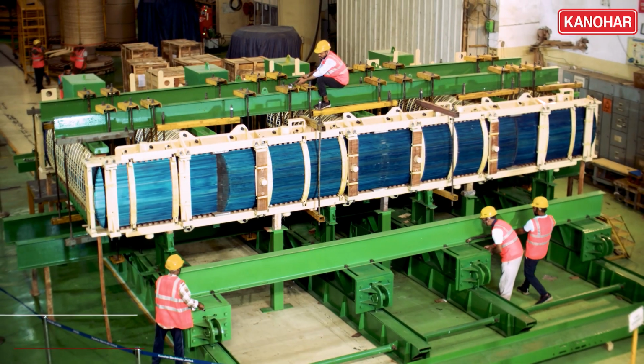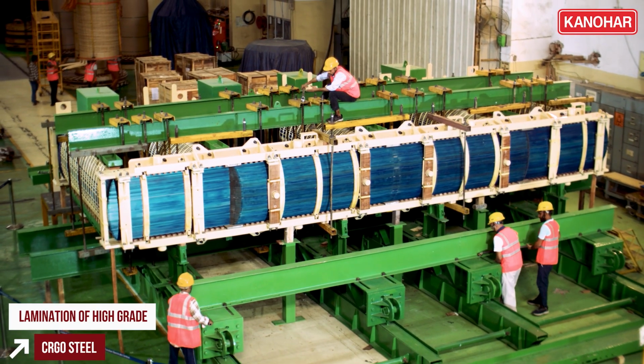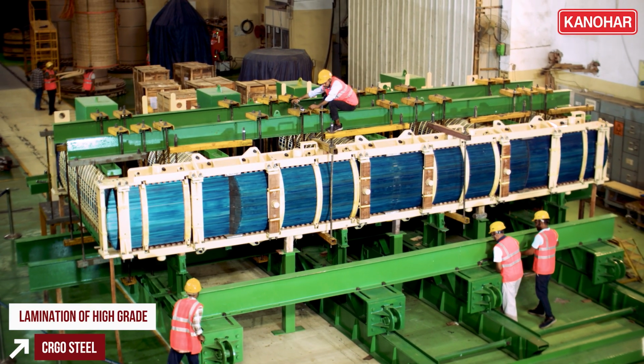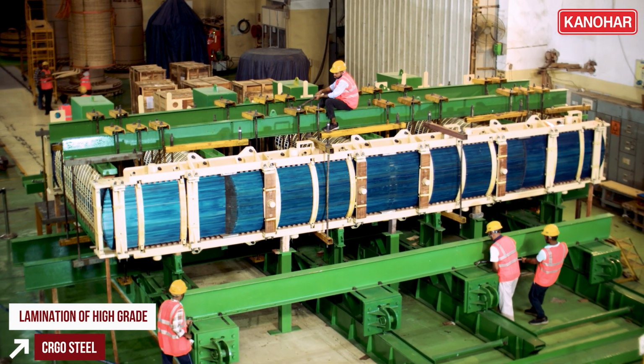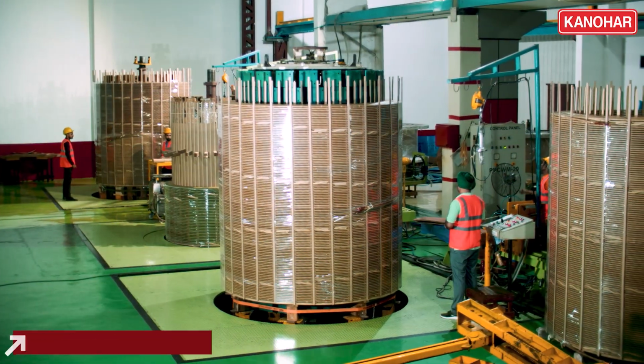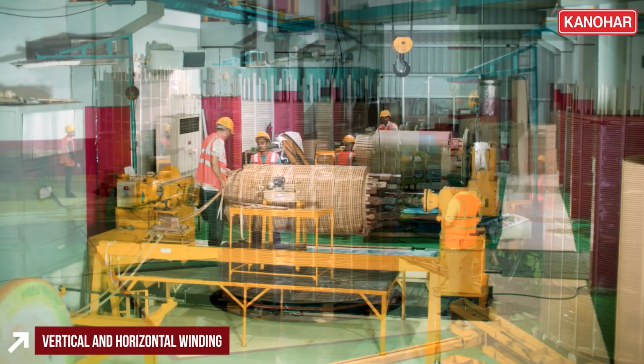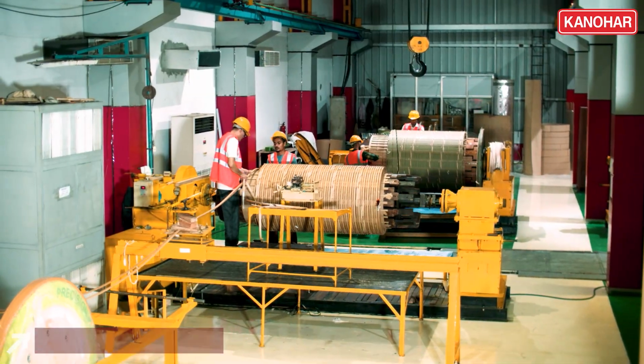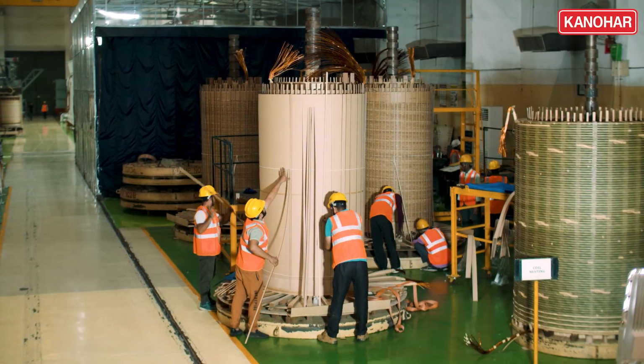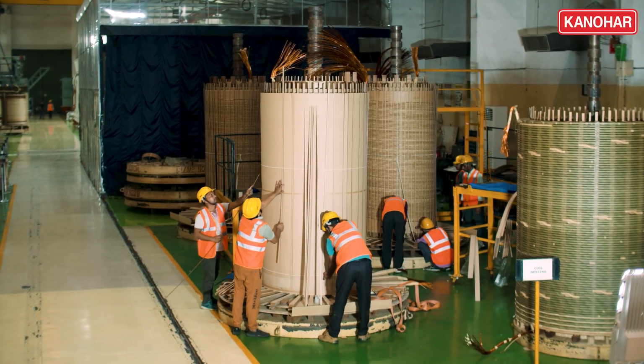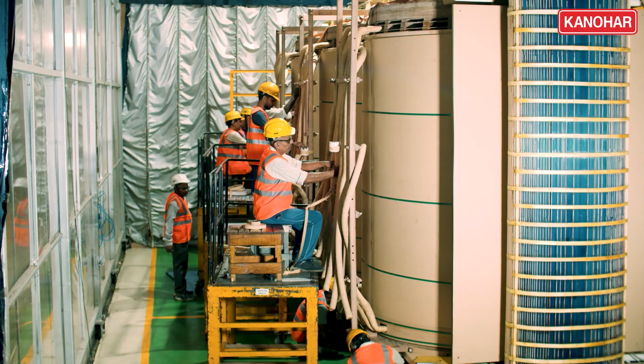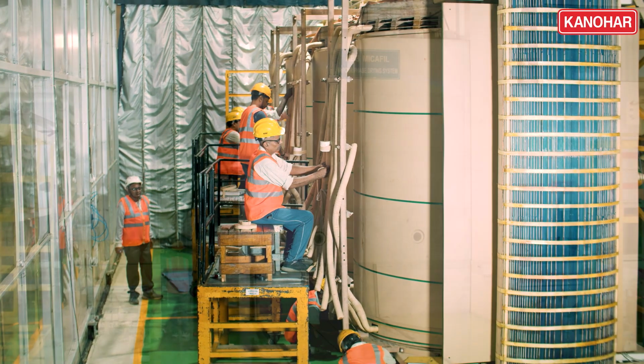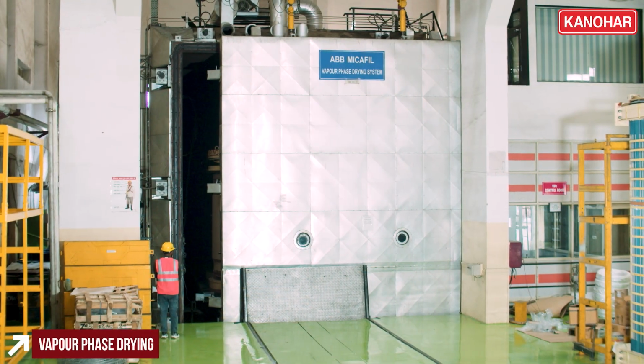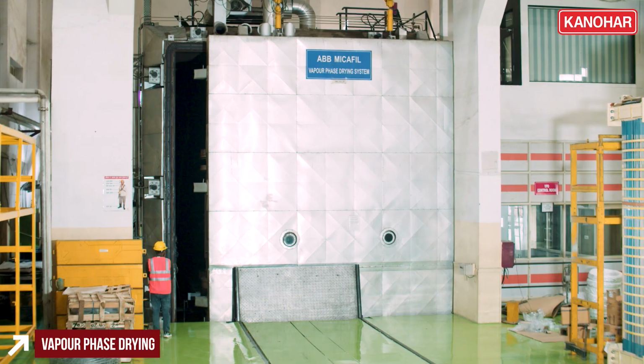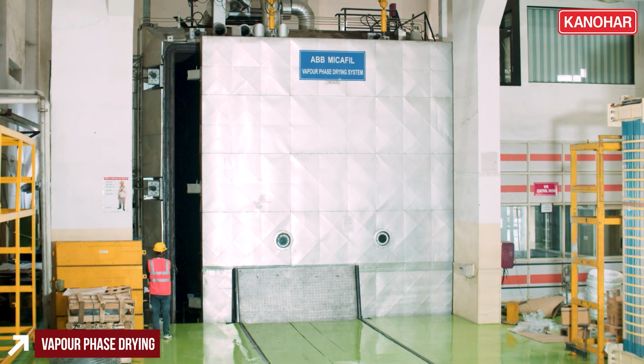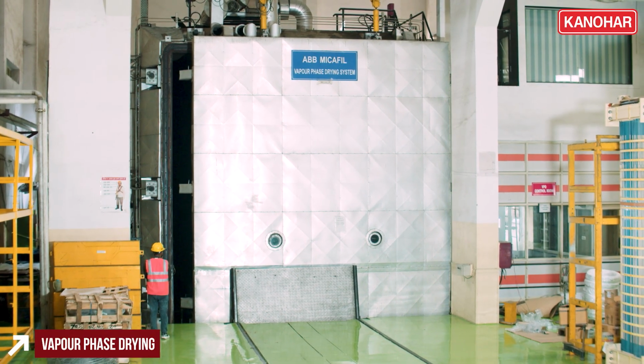On the shop floor, laminations of high-grade CRGO steel are stacked to form a precision core. Windings built on vertical or horizontal machines are compressed and stabilized under controlled pressure and temperature for long-term mechanical strength and insulation life. The core and coil assemblies are then dried in vapor phase ovens, guaranteeing deep removal of moisture.